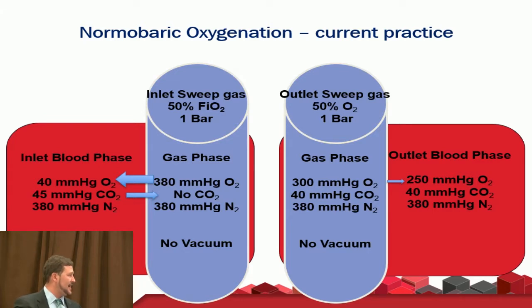It's low in O2, high in CO2, and the rest is basically nitrogen. So we pump in high oxygen gas in the gas phase that has no CO2, and we get diffusion. Diffusion gradients exist: O2 goes into the blood, CO2 comes out. Leaving the oxygenator, we've got oxygenated blood, a good arterial CO2, and whatever's left in the gas phase stays in the gas phase.